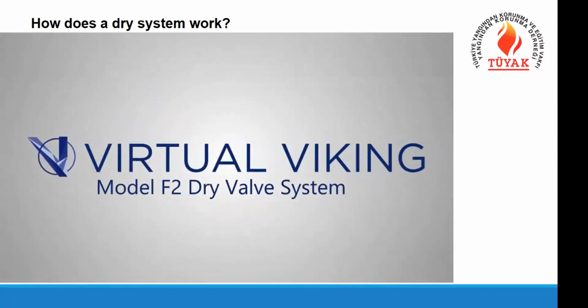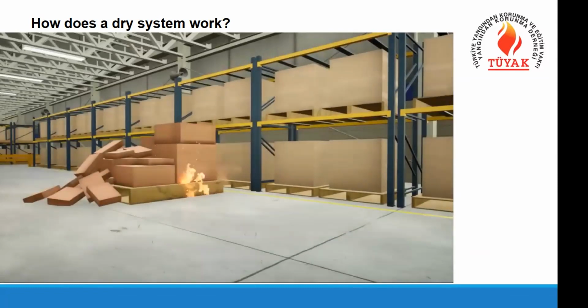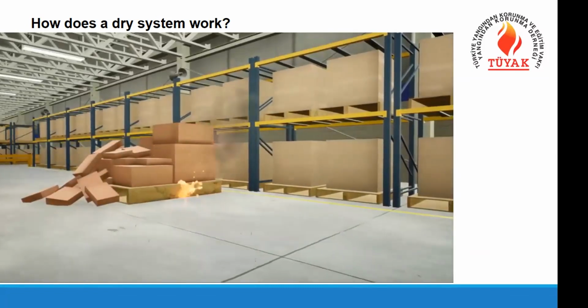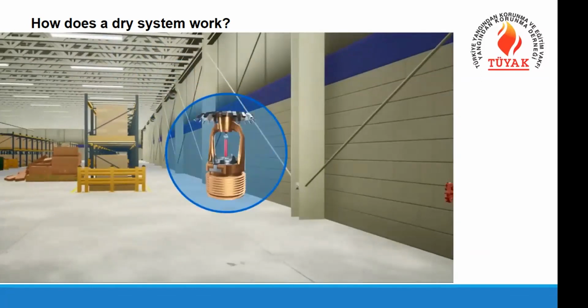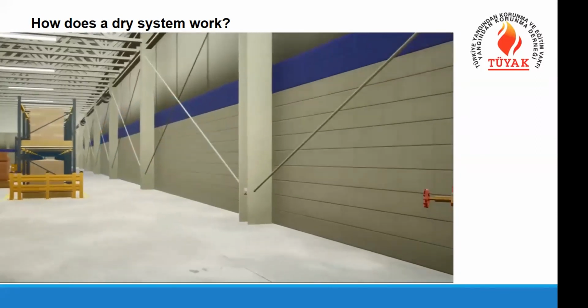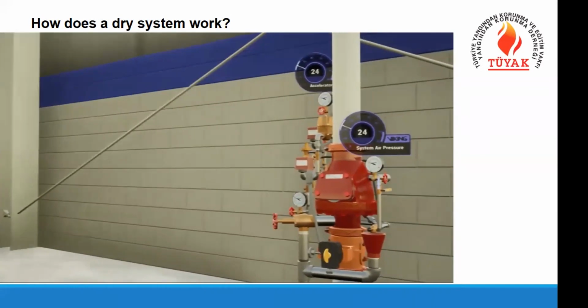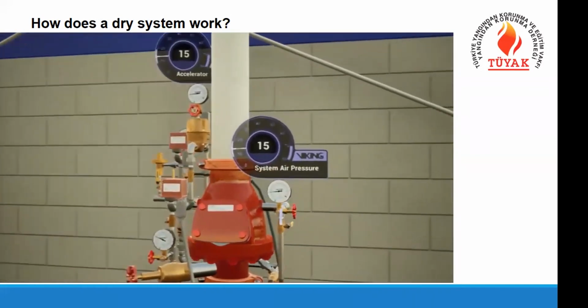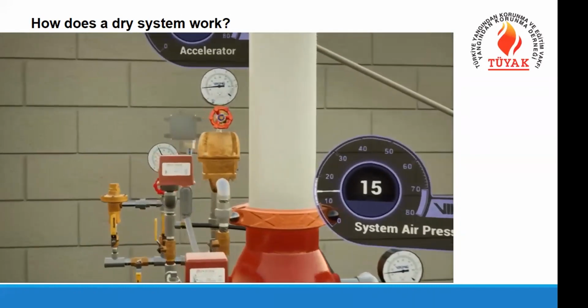These kinds of systems are especially used in unheated areas subject to freezing. A fire has started in the building. As the fire grows and the heat reaches the sprinkler's rated temperature, the temperature-sensitive device and the automatic sprinkler operate. The temperature-sensitive device could be a frangible bulb or a fusible link. Once it operates, either the pip cap or the seal will be displaced by air pressure. Air escapes through the activated sprinklers, causing the air pressure within the outlet chamber of the valve, the trim, and the pipes to drop.